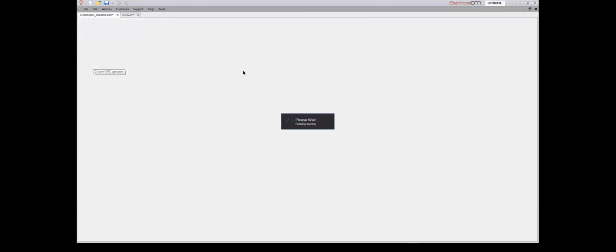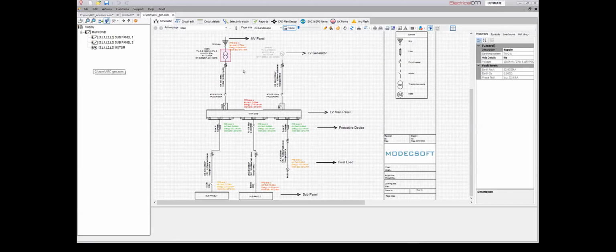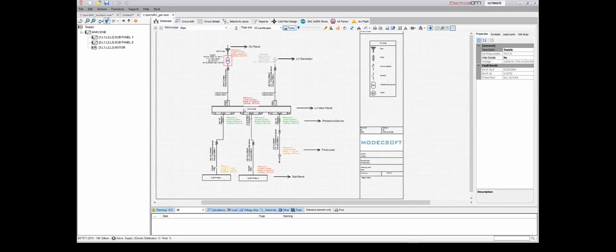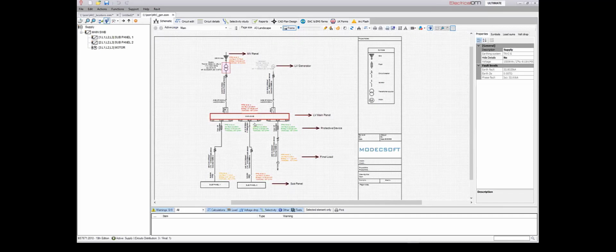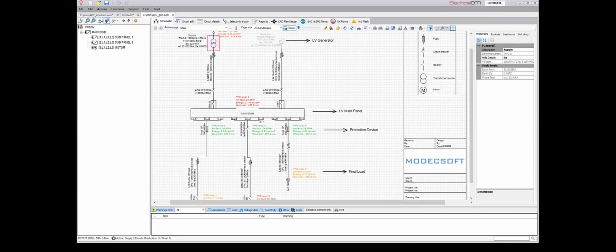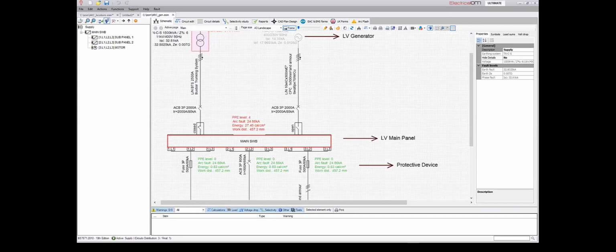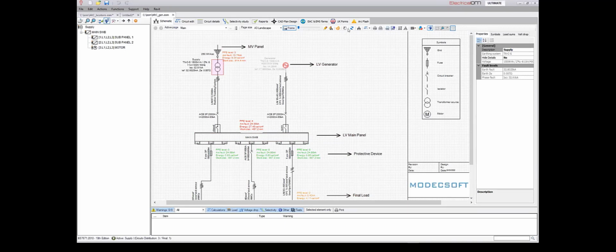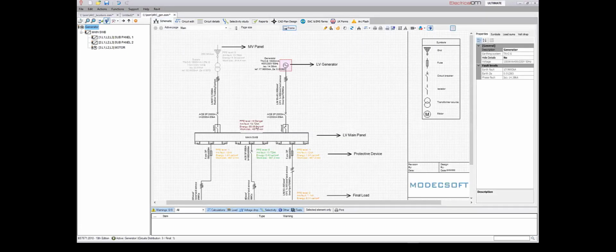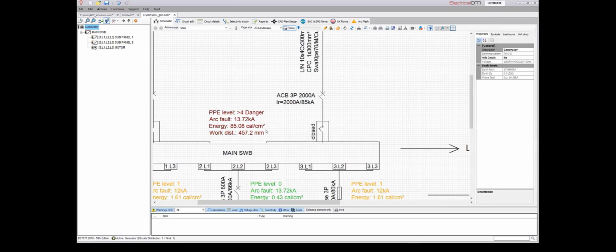Another case that is important to demonstrate is when we may have a backup generator in the system, or another source that is not the same as the essential, or the main supply. Now, in this example, which is the same example as before, we can see that the PPE here is 4. But if we enable the generator, which provides a smaller fault level, and refresh the arc flash calculations from here, we can see that the PPE has exceeded 4.